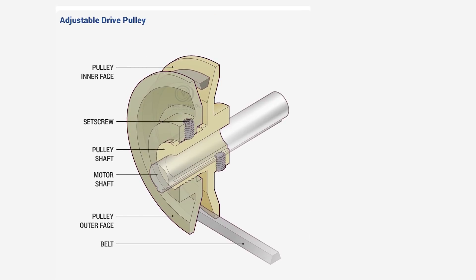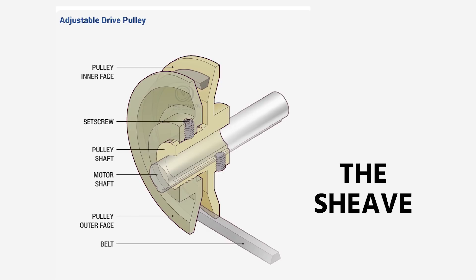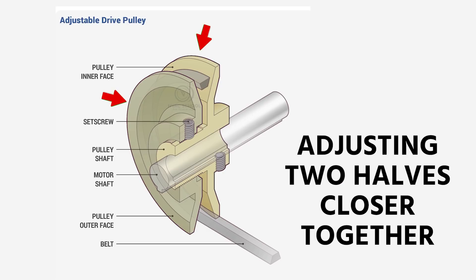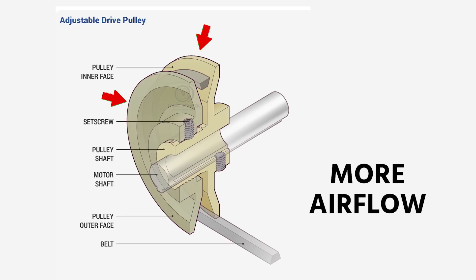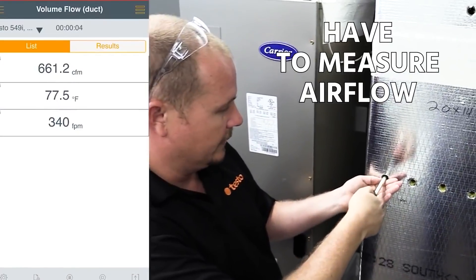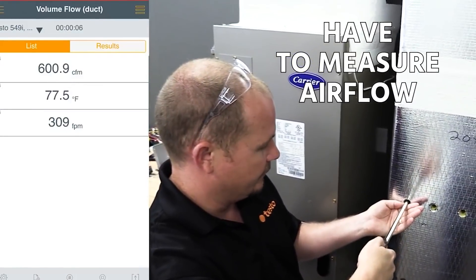In this image you can see some of the different components to the adjustable drive pulley — the one we call the sheave. With the adjustable drive pulley, adjusting the two halves closer together results in more airflow, and adjusting them further apart results in less. That's only something a test and balance organization or somebody doing commissioning would set, because you have to measure airflow to do that properly. In the field, we are not going to be adjusting that adjustable drive pulley.